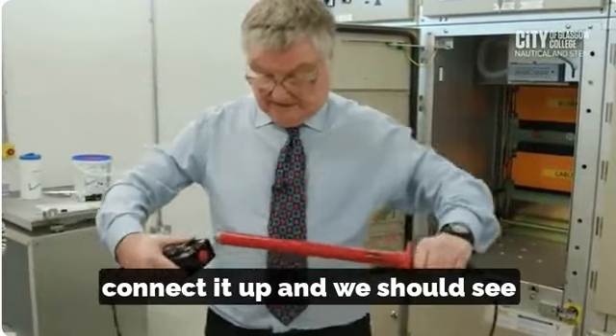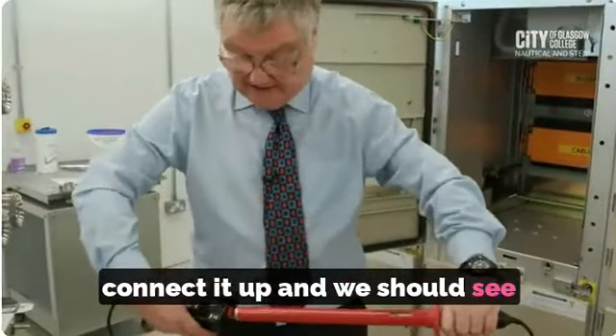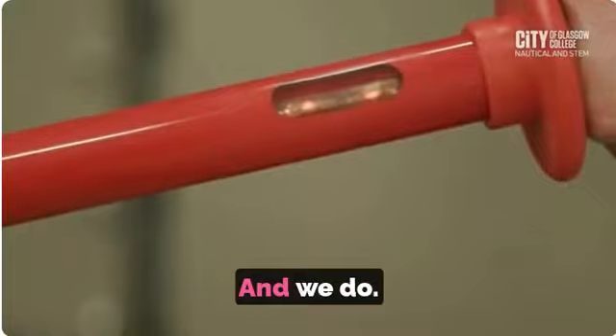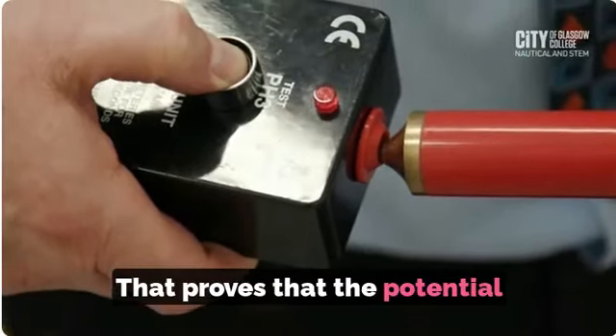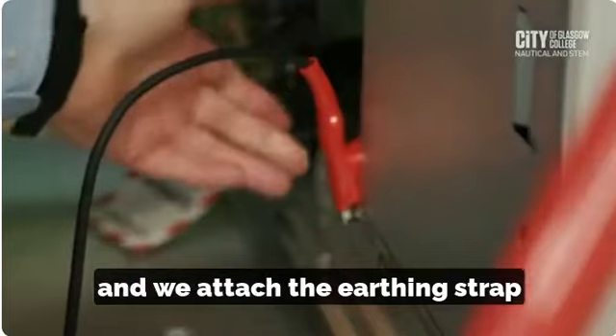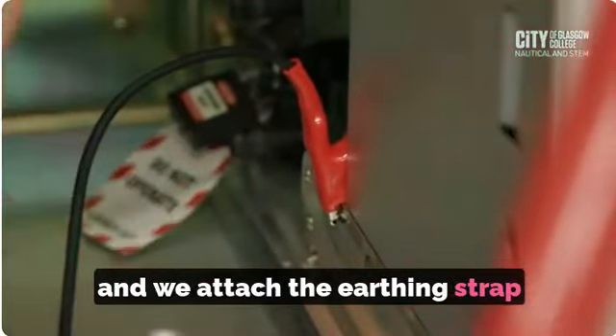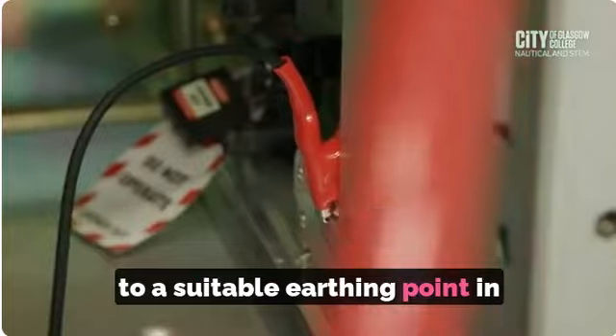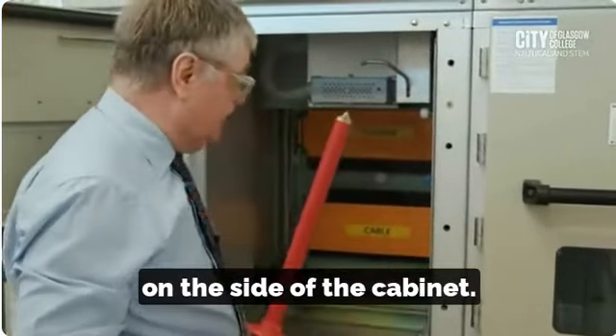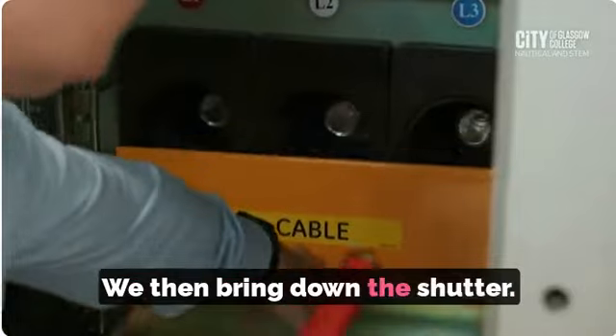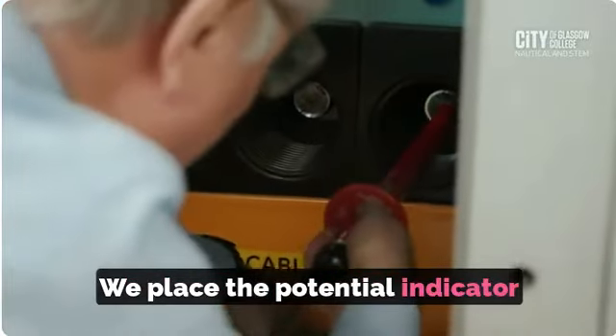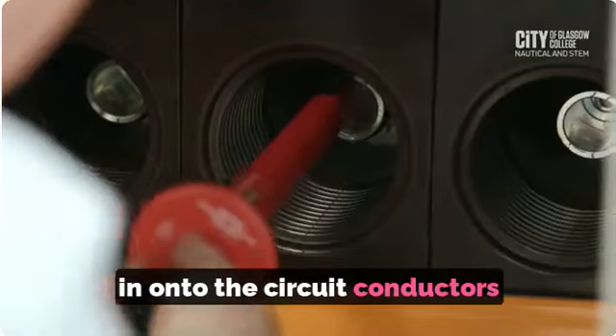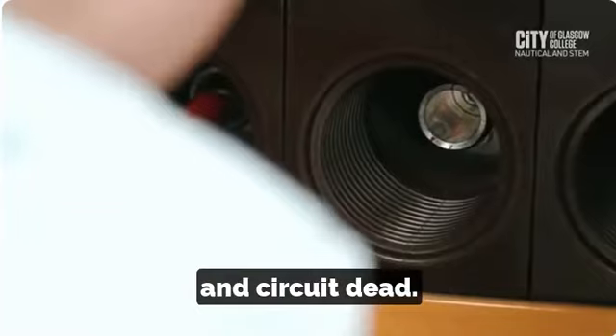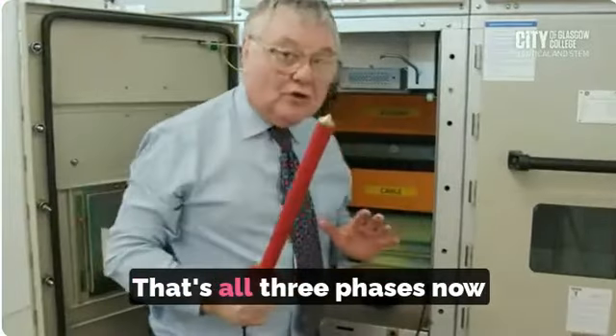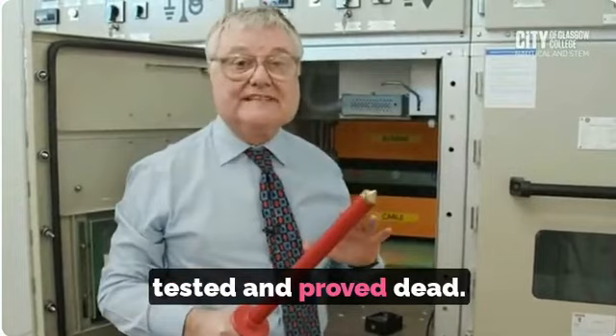and connect it up, and we should see the xenon lights glowing, and we do. That proves that the potential indicator is working correctly. And we attach the earthing strap to a suitable earthing point, in this case a piece of aluminium on the side of the cabinet. We then bring down the shutter, we place the potential indicator onto the circuit conductors and circuit dead, and circuit dead. That's all three phases now tested and proved dead.